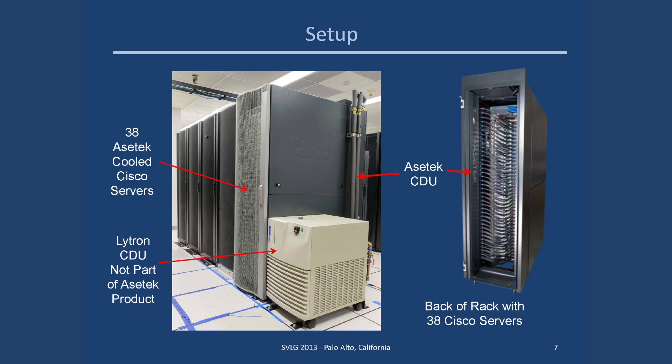Here's the setup. On the left, 38 Asetek-cooled Cisco servers are racked. In the foreground is the Lytron CDU — this is not part of the Asetek product; it was used to adjust the water temperature for our tests. On the right you can see the back of the rack with the Asetek CDU on the side, which is part of the system, along with the supply and return tubes that take water to and from each server.